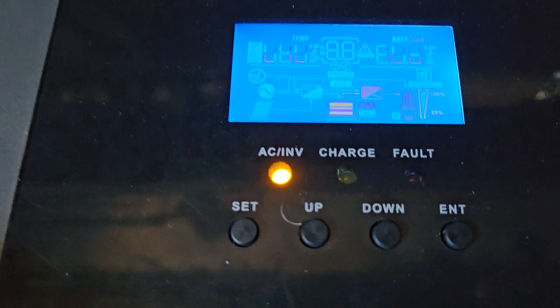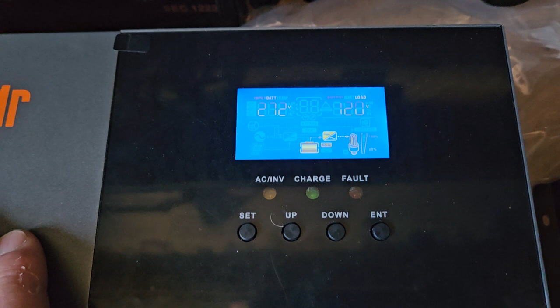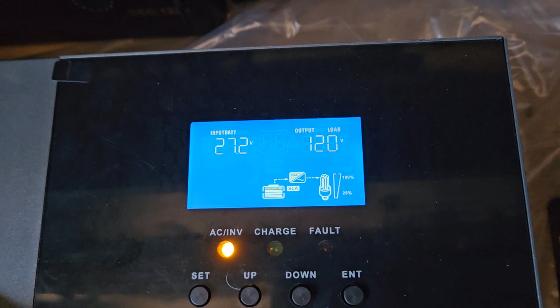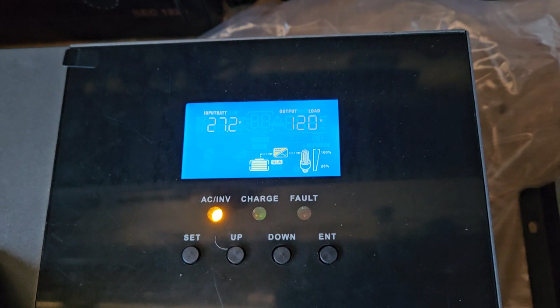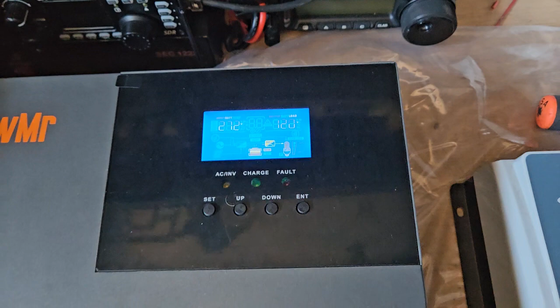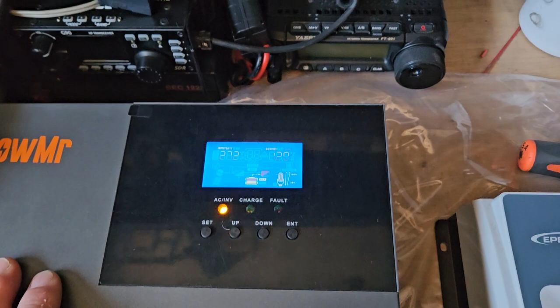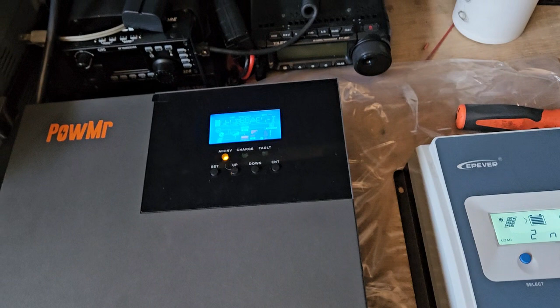The problem with this unit I've found is that you can plug it into the grid and set up different parameters, but it doesn't seem to want to kick the grid on until the battery is at a low set point where it's already bad. It kicks the grid in when basically there's no solar, the battery is terrible, and now you're going to disconnect from your load because you don't have enough power.